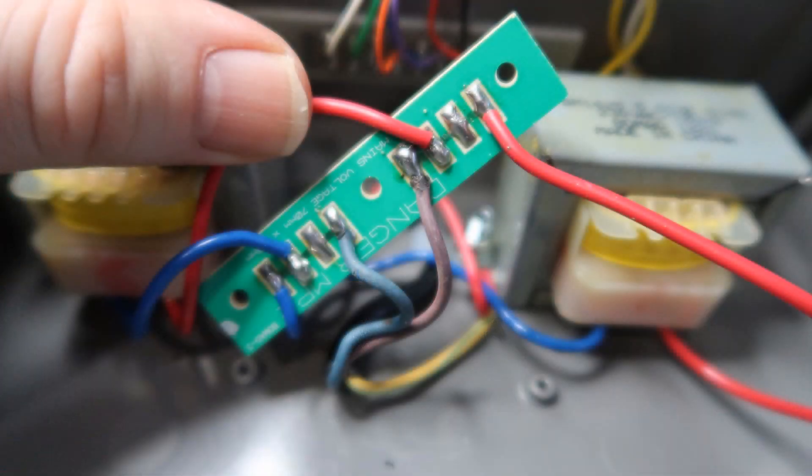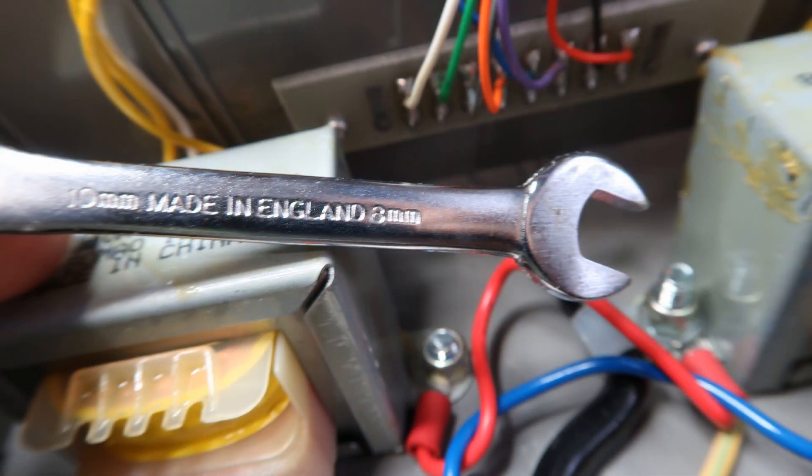Remove the screws from the mains commoning PCB. Unsolder the live and neutral wires — only the incoming wires need to be removed. To undo the secure nut from the transformer mount and earthing point you will need an 8mm spanner.